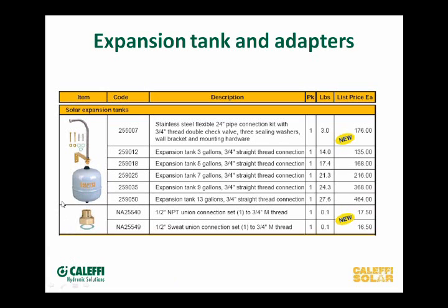The way the double check valve works: when you screw the tank into the check valve, the nipple on the tank actually pushes the check valve open, allowing fluid in and out of the tank. When you take them apart to service them, you break the union — don't unscrew the tank from the thread. The tank has a nice big brass union there that you break apart, and then you can remove the tank without losing any fluid from either side.